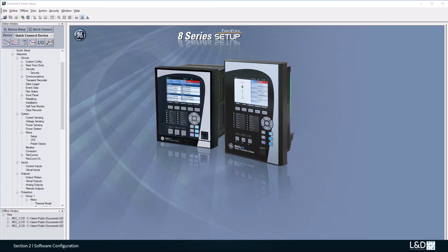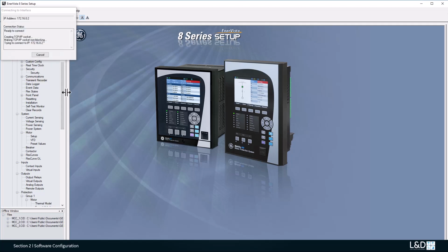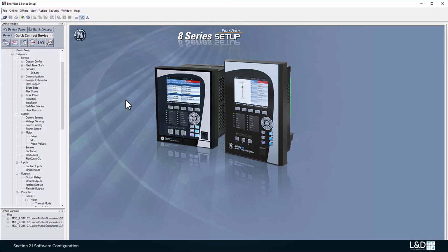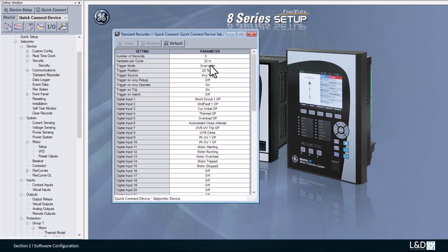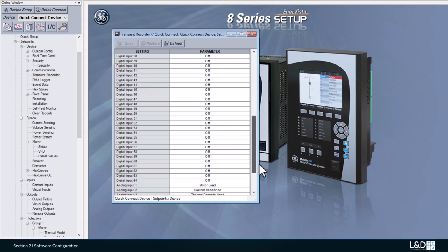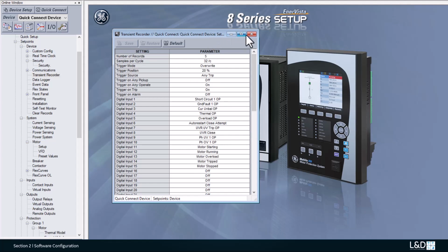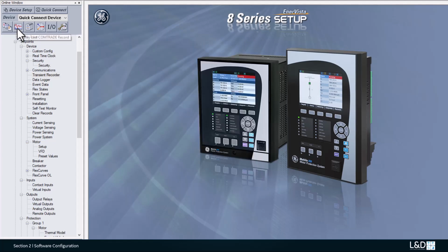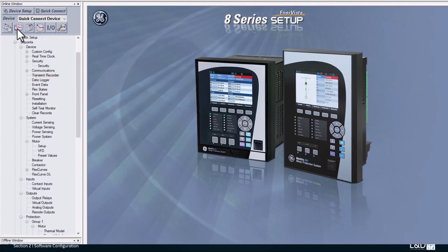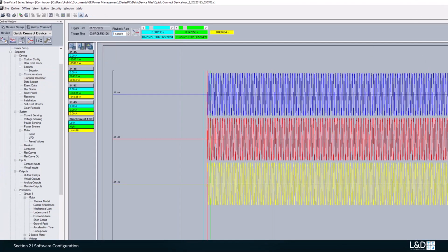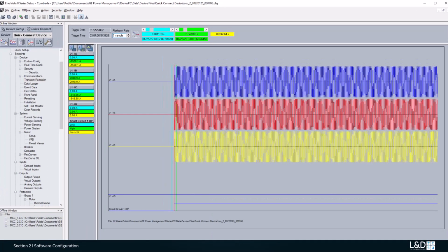The waveform in the 369 has only the trigger position setting, but in the 859 there are lots of settings under the transient record. So not only the trigger position, but we have the trigger mode and the trigger on digital and analog inputs. So we have much more information here, and we have shortcut hotkeys to click. By clicking this Comtrade, the record, we can see the waveform. And for this one, we got a pre-triggered waveform, 3 waveforms for the short circuit.